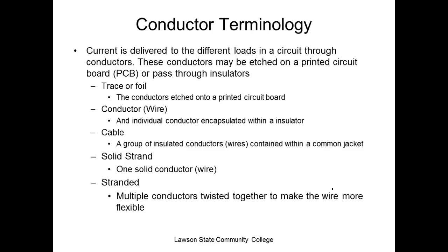terminology. So we have what we call a conductor. Everybody okay with that? Usually when we use the term conductor, we're talking about a conductor that's encapsulated in what? Insulated. And what's the insulator on there for? Protection from the environment. Well, yes and no. In conductors, we learn two terms. We learn what we call a jacket, and we learn what we call an insulator. The function of the insulator is to keep that push in. That way I can handle the wires, or I can bring wires close together and we don't have contact with it. The function of the jacket is to protect the insulator from the environment.